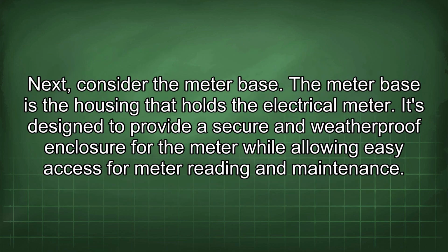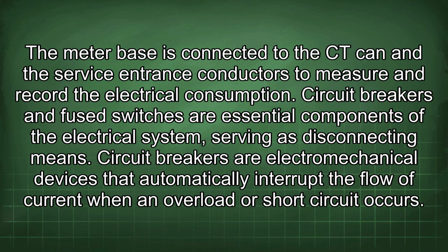Next, consider the meter base. The meter base is the housing that holds the electrical meter. It's designed to provide a secure and weatherproof enclosure for the meter while allowing easy access for meter reading and maintenance. The meter base is connected to the CT can and the service entrance conductors to measure and record the electrical consumption. Circuit breakers and fused switches are essential components of the electrical system, serving as disconnecting means.